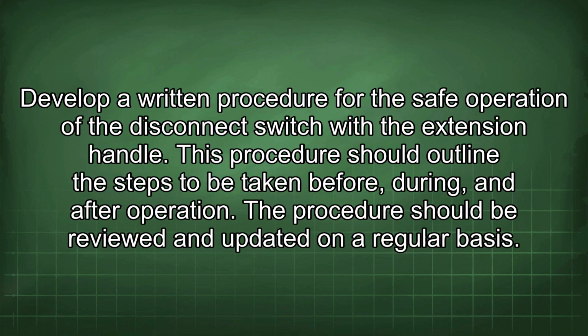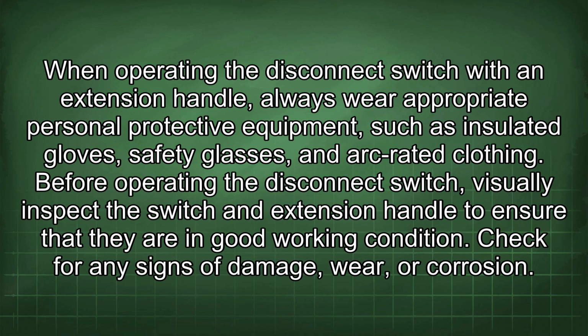Develop a written procedure for the safe operation of the disconnect switch with the extension handle. This procedure should outline the steps to be taken before, during, and after operation. The procedure should be reviewed and updated on a regular basis. When operating the disconnect switch with an extension handle, always wear appropriate personal protective equipment such as insulated gloves, safety glasses, and arc-rated clothing. Before operating the disconnect switch, visually inspect the switch and extension handle to ensure that they are in good working condition. Check for any signs of damage, wear, or corrosion.